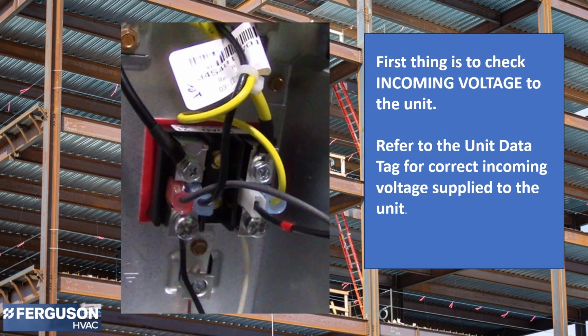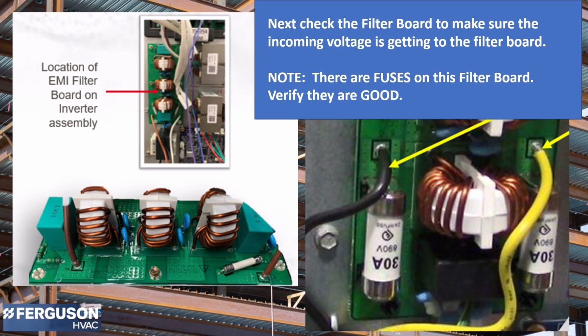So when checking an inverter that's not working, the first thing to check is the incoming voltage to the unit. Refer to the data tag for the correct incoming voltage supplied to the unit. Most inverter products have a filter board to filter out interference from the incoming voltage. So next, check the filter board to make sure the incoming voltage is getting to the filter board. Note, there are fuses on this filter board. Verify that they are good.